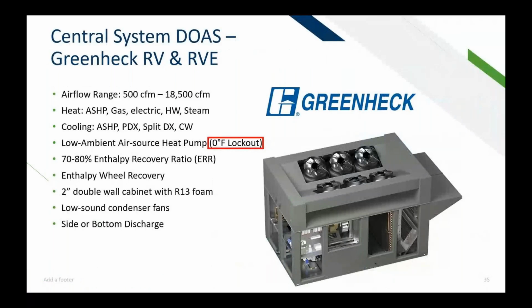So, moving on, we have another great central system DOAS that I would really like you to consider for any of your projects, whether it's with a Group R building or beyond, any sort of commercial building. Up to 18,500 CFM. Greenheck makes a really great air source heat pump unit that can pair with this. They also, of course, have gas, electric, hot water, or steam, or packaged DX, split DX, or chilled water. But know that air source heat pump does have a true 0-degree lockout.